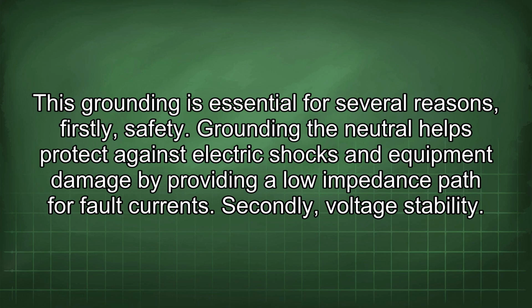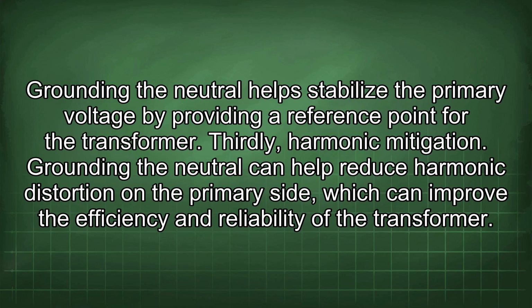Firstly, safety. Grounding the neutral helps protect against electric shocks and equipment damage by providing a low impedance path for fault currents. Secondly, voltage stability. Grounding the neutral helps stabilize the primary voltage by providing a reference point for the transformer. Thirdly, harmonic mitigation. Grounding the neutral can help reduce harmonic distortion on the primary side, which can improve the efficiency and reliability of the transformer.